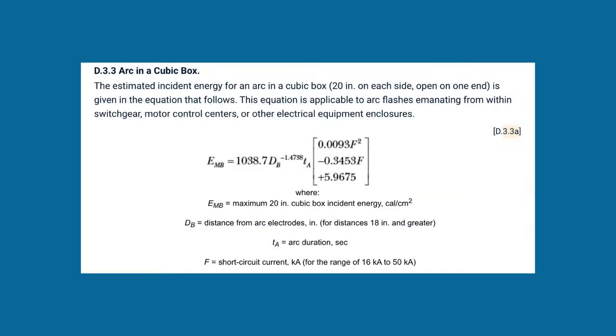Now, watch this. Now you go to an arc in a cubic box. Now they're going to tell you this is where the arc is going to be contained inside. In other words, it's going to produce more of an arc because it can't escape into free air. So they tell you what is considered a cubic box. This is 20 inches on each side, and it's open on one end. Okay? So you'll look here, E sub MB. They'll tell you that's the maximum 20-inch cubic box.